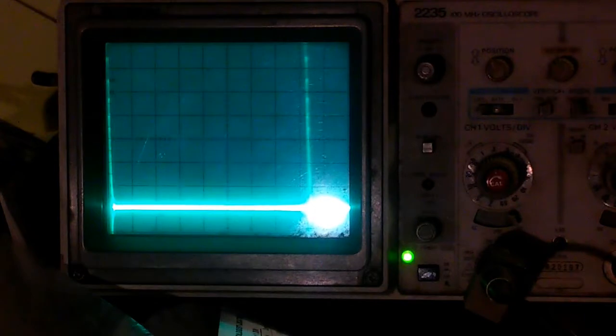You see our output pulses are now at a fixed rate. They're coming much slower, about 33 hertz. Look at the feedback signal, and it's more like 6 volts. So the output is feeding back the information to the chip, telling it that the voltage is too low, and it needs to pick up the pace, but the chip isn't responding for some reason.